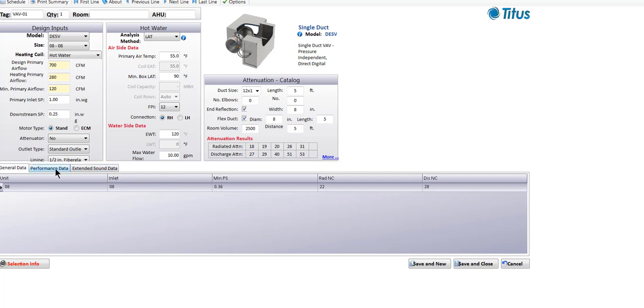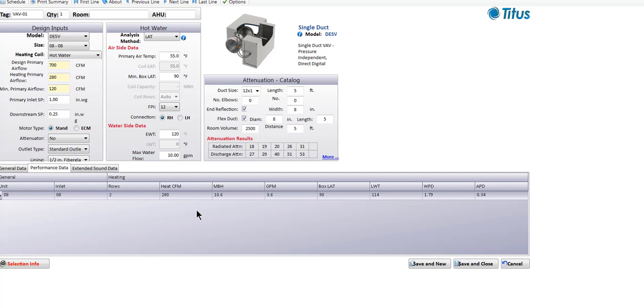The point of this exercise was to show you that with 180-degree water, we got a selection with a one-row coil. With 120-degree water, we got a three-row coil. But when we changed from 10 fins per inch to 12 fins per inch, we were able to drop back from a three-row coil down to a two-row coil.